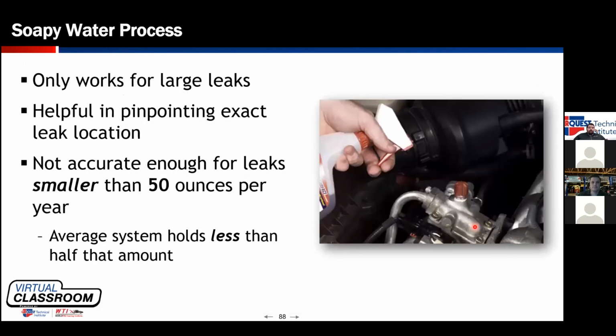Again, soapy water works for some leaks. Again, it depends on access. The generally accepted rule is that soap bubbles will start to form on leaks larger than 50 ounces per year. So if you're finding a leak with soap bubbles, it is probably a rather large leak. But it can be useful sometimes.